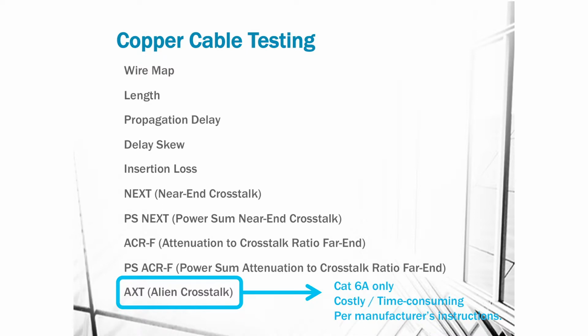If you've got a Category 6A cable, if you got a client that's just Cat 6A everywhere, we don't need the 10 gig speed, but we have to meet their cabling, an owner's cabling standard. Alien crosstalk is costly and time consuming to test, and it's per manufacturer's instructions is what I write in there, because it varies from manufacturer to manufacturer, and not every cable is tested just because it's so costly and time consuming to do. So there may be a 10% sampling for that.